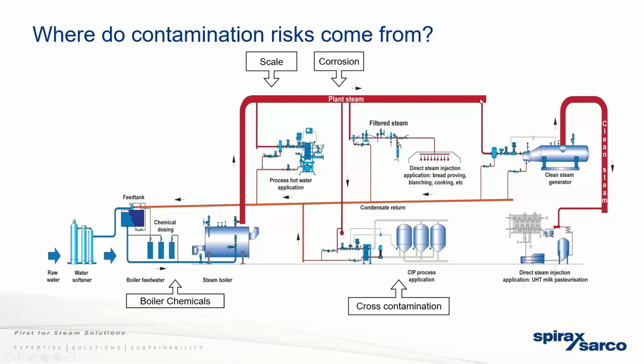heater. In this slide here, you can also see a clean steam generator on the end. This is another method when you're going to direct steam injection: you can use that plant steam as the heat and energy source for a clean steam generator. The clean steam generator would just have potable water without any chemicals. From that point, all the piping would be stainless, so you won't get the scale and corrosion in the pipework. And from there, you can use it for direct injection. So this is one method that you can use for hose stations. Although it's taking away the food safety risk, it's not taking away the risk to employees if there is a failure.